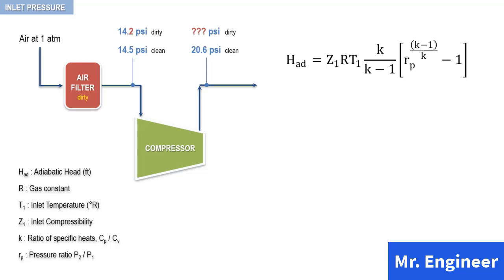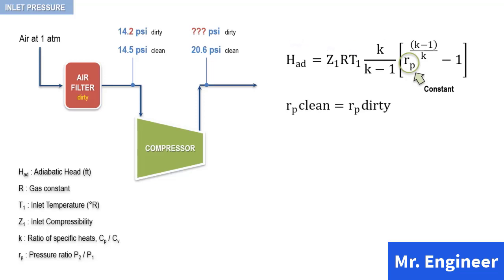For a given inlet volume flow at a given rotational speed, the head output is constant. And in our case, because there is no change in the other inlet conditions, the pressure ratio does not vary. Therefore, the pressure ratio for the clean condition equals the pressure ratio for the dirty condition.